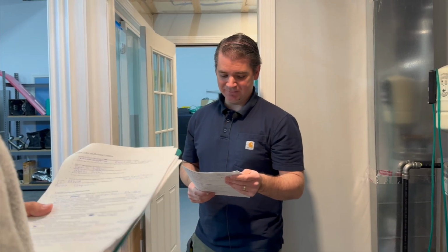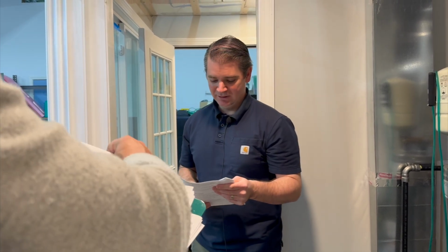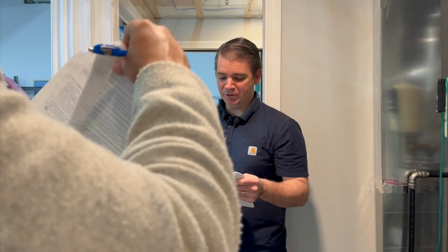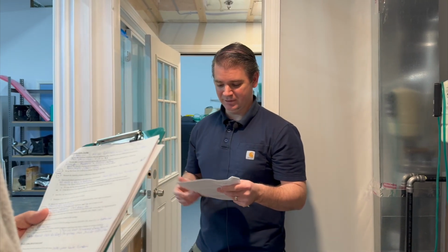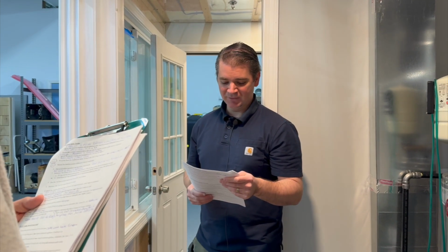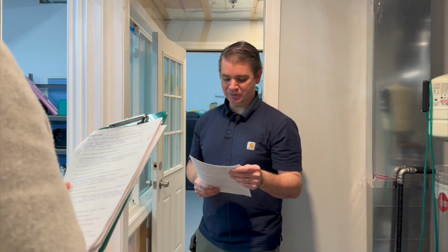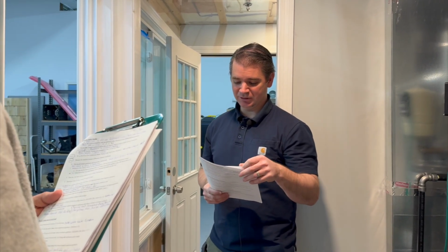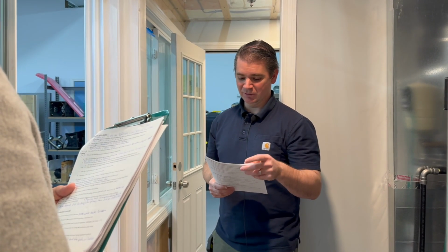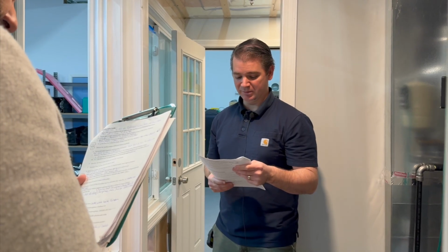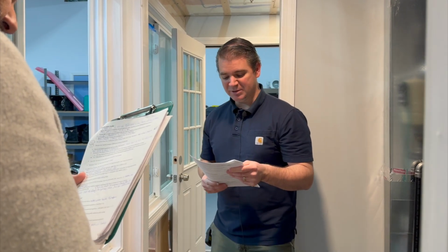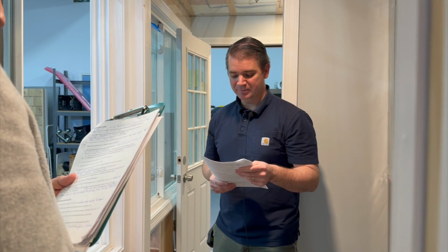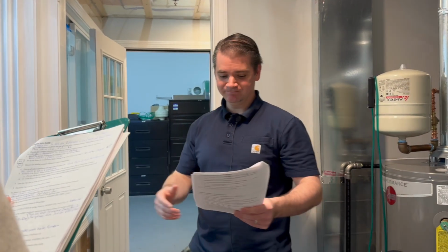Combustion safety testing. Discuss one common condition that can adversely affect baseline pressure differential measurement. Pinched tubing or stepping on the hose. Discuss one common corrective action that can stabilize baseline pressure under adverse conditions. So if it's windy, we can do the time averaging on the manometer. Identify the specific location and boundaries of the CAS, and then the others. We only have the one CAS, so basically it's just this one small room.